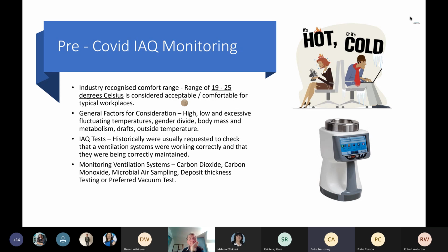You then fit the cassette onto the tube from the pump, and then you have another piece about 5 centimetres in length on the other side of the cassette, and you physically hoover the ductwork, and it draws it up into the cassette. And you don't draw the pipework across the ductwork any faster than about 5 centimetres a second. Once you've completely vacuumed it, you can take the pipes off either side of the cassette. Then you put the plugs back in, and they get sent away for a site analysis and weighed. And then the weight of the dust, in the table that Robert showed earlier, will tell you whether you need to get your ductwork cleaned or not.